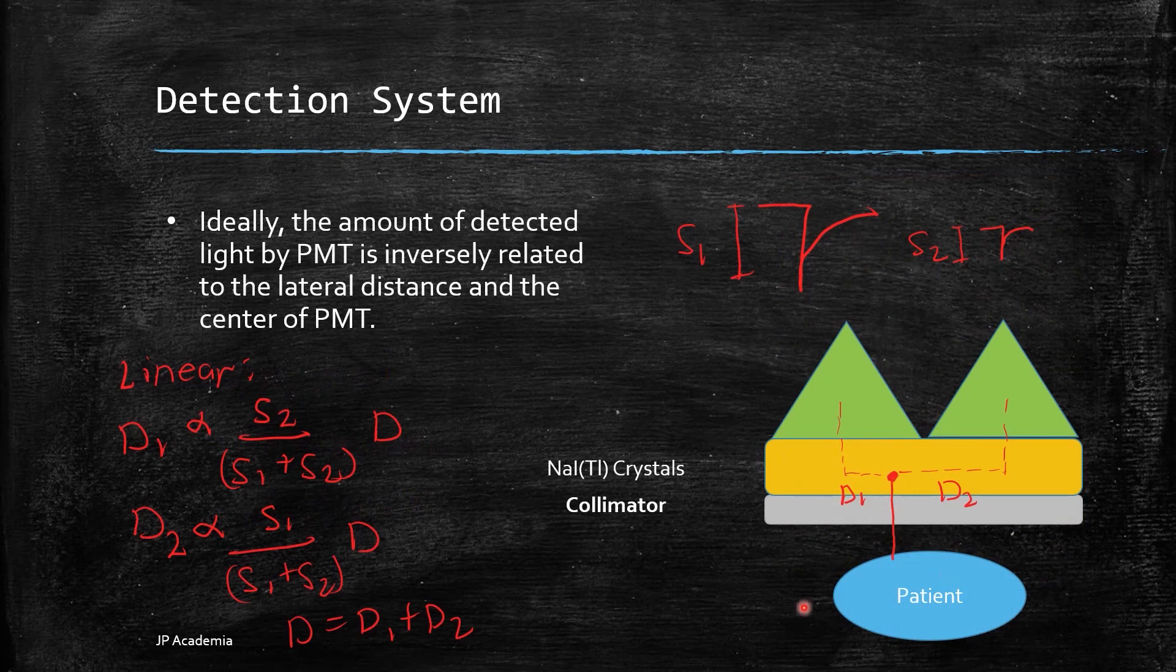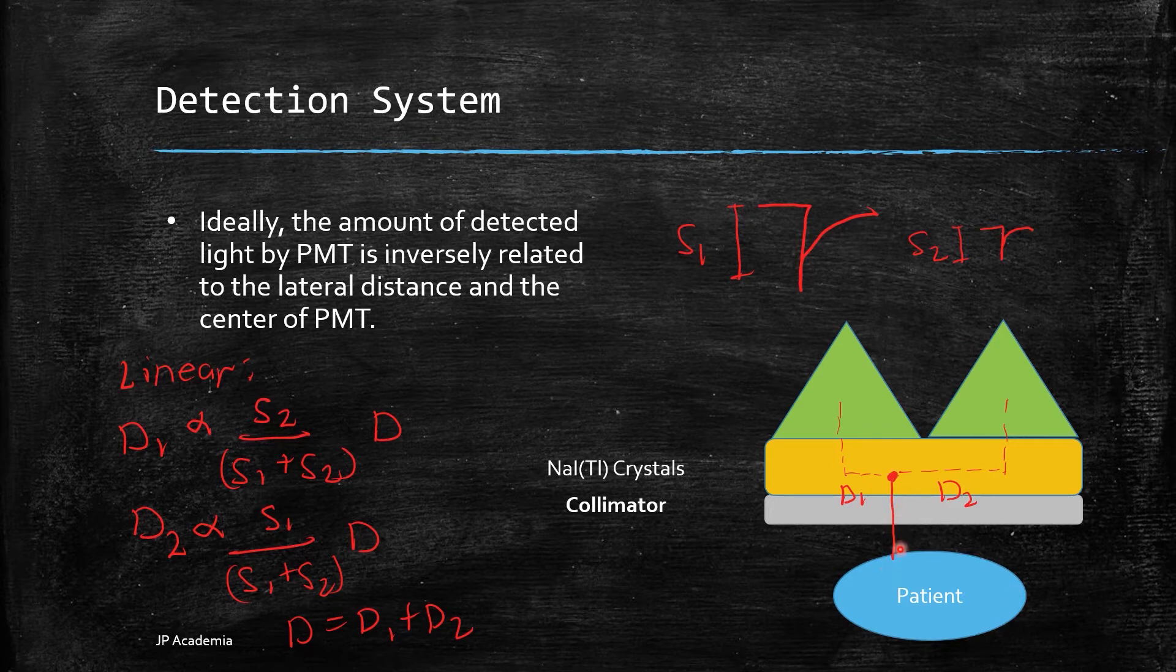Now, let's go to this illustration. Let's say we have a patient emitting gamma ray, a single event. Then this single event is detected by the system with the collimator and the scintillation crystals. D1 here and D2 refers to the lateral distance with respect to the center of our PMTs.